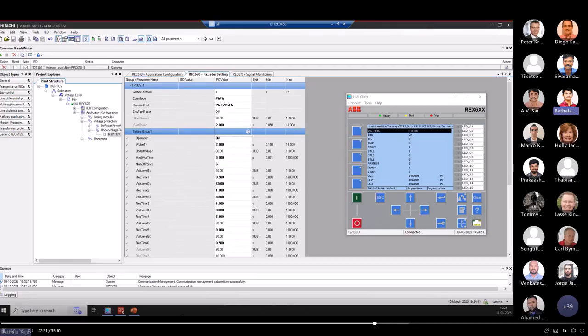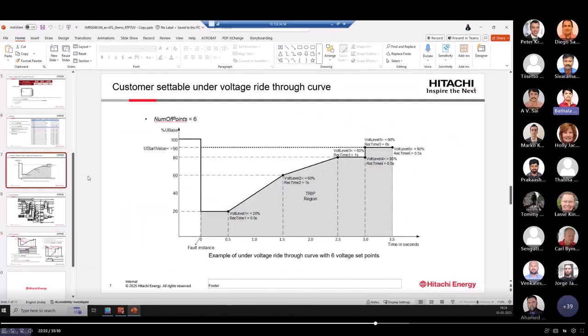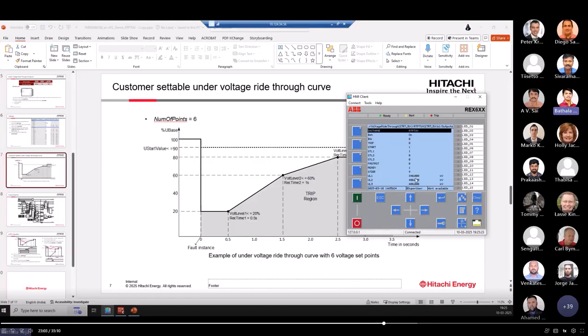Why is it happening? If you go to the curve here, I am providing 85% and keeping that 85% continuously. So it is entering the trip zone at the end of the curve. That's why after a long time we have seen trip, and trip is resetting after trip TR, which is set as 2 seconds. That is again to show for some time. So trip came for 2 seconds and it has reset. But I maintained 85%, so start is not resetting at all.